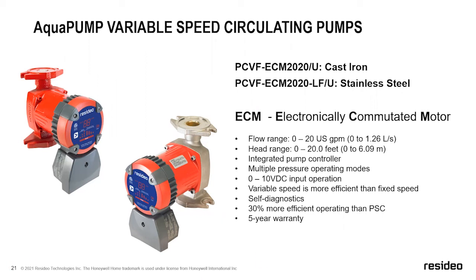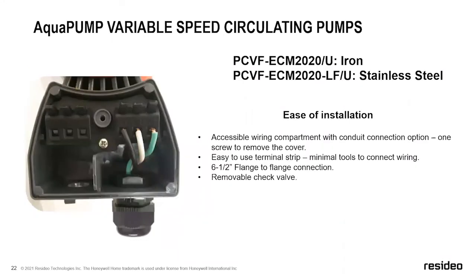What we've done with our circulator is it is kind of our premium offering compared to other brands that exist. We have a digital display that's going to flash back and forth between flow rate and wattage consumption. We have 4 different variable curve settings, 3 fixed speed settings, auto adapt, and it will take a 0 to 10 volt input signal. We're also continuing our 5-year warranty, which is what we've had on our 3-speed pumps for as long as I can remember. And then just one point I wanted to bring up, when we look at overall efficiency of systems, there is roughly a 30% increase in circulator efficiency when you go to variable speed versus fixed speed. I get asked that question a lot, so I wanted to touch on that.